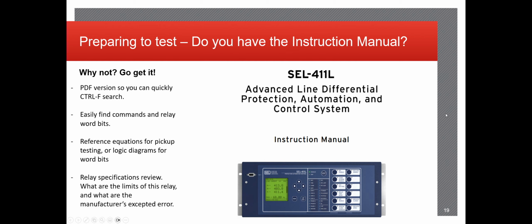Instruction manual. That is your best friend when you're running into issues with your testing. It will provide all the information you need. You just got to look for it and understand how to apply it to your test. PDF versions are the easiest nowadays because you can just Control F search stuff, especially relay elements that you're trying to pick up or find. You can find the commands, word bits, reference equations for pickup testing or logic diagrams. Those are super beneficial because you may be missing something in your relay test setup that you won't figure out until you actually look back in the manual.